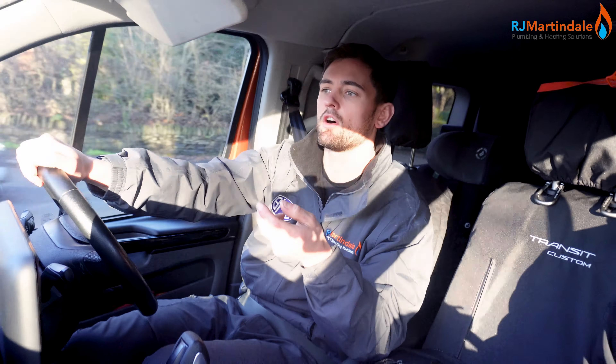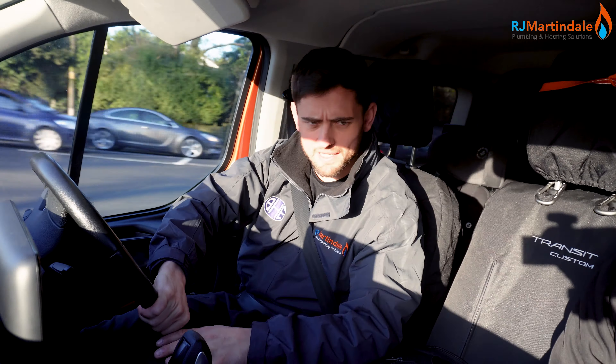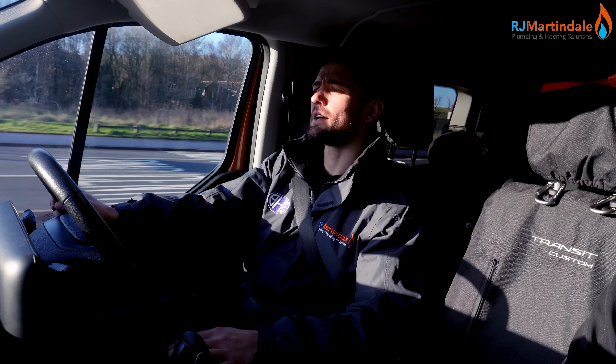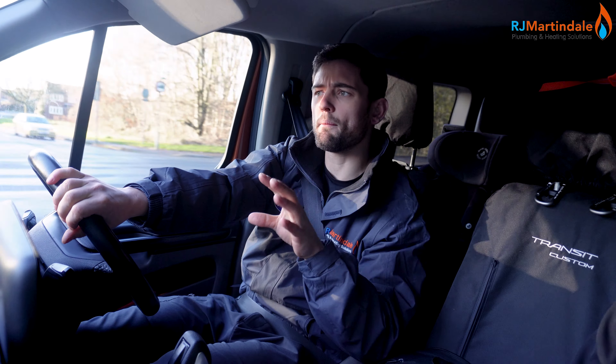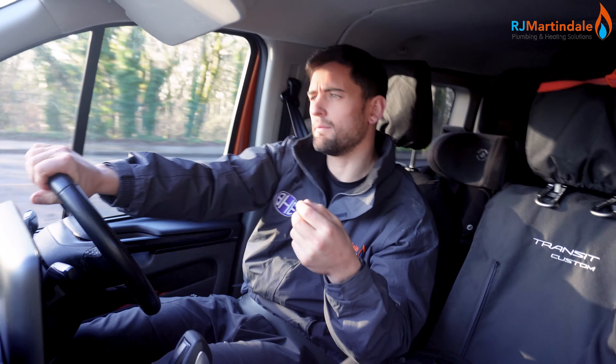That was a bit of a weird one. I don't normally physically get involved with the wiring - I try and just act like technical support over the phone so engineers wire it themselves. My lads are miles better now - from your standard combis wiring EPHs to Hives, to wiring S-plans and Y-plans. That job was a heat-only boiler to system boiler. On the system boiler we just need a live, neutral, earth and a switch live - we've got the pump built into the boiler, unless you start doing hot water priority or dealing with integral diverter valves whether it be Worcester or Viessmann.